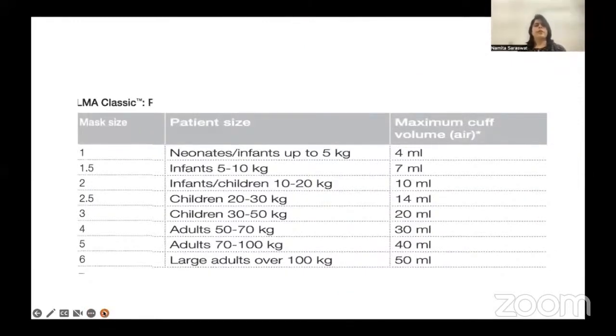Now, you should know that the size of the device is selected by knowing the weight of the patient, and the weight of the patient and size, everything is written on the LMA. Maximum cuff volume you have to remember. For device 1 you will put 4 ml, 1.5 is 7 ml, for 2 it is 10 ml, 2.5 is 14 ml, and later on you can just use this formula, like for number 3 device, 3 minus 1 into 10, that is 20 ml, and so on.